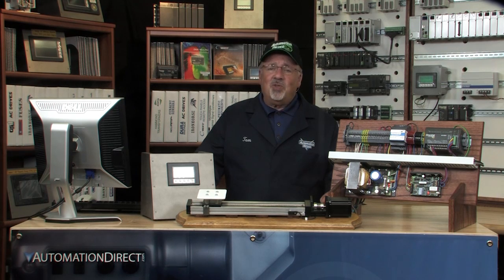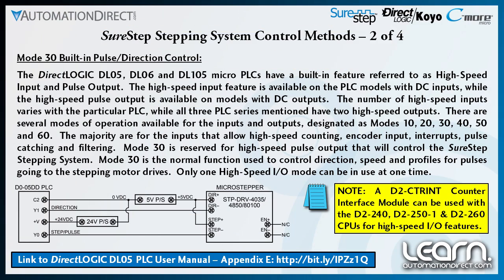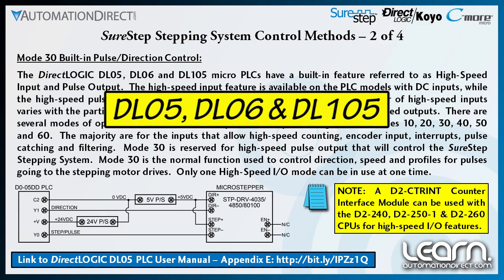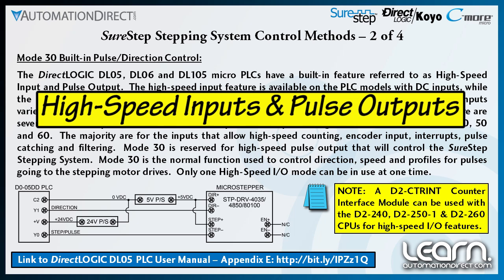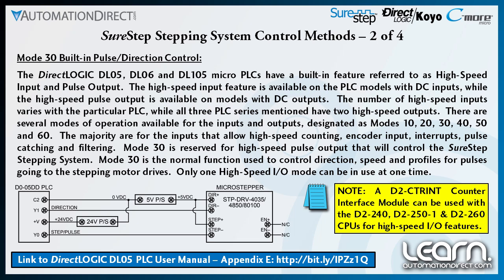Some of the AutomationDirect DirectLogic PLCs, such as the DL05, DL06, and DL105 families, have built into them a high speed input and pulse output feature. Keep in mind that the high speed input feature is available on PLC models with DC inputs, while the high speed pulse output is available on models with DC outputs.